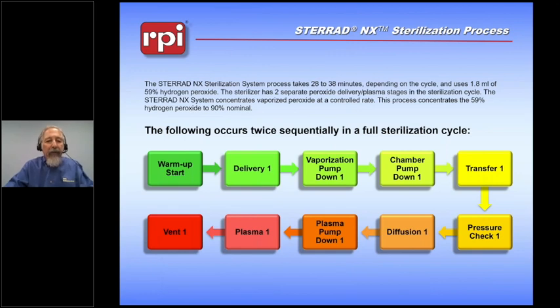Okay, so this is what the peroxide process looks like. Basically, what we do is we put our material into the chamber. We allow all of our surfaces to acquire the correct temperature so that we can control where the hydrogen peroxide is and where it winds up going. And then once that system is warmed up, we deliver the peroxide from the chamber to the vaporizer, pump down the vaporizer.